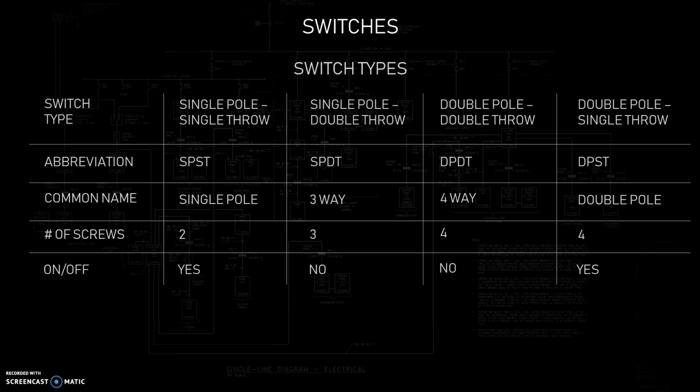So it's a nice quick check in the field to make sure, hey, am I actually dealing with a four-way switch here, or am I actually dealing with a double pole switch? Well, do we have an on-off? If so, it's a double pole. If not, it's a four-way. And four-ways are far more common than the double pole.